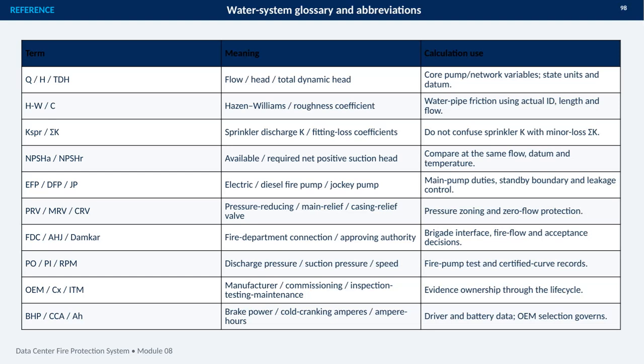This reference slide brings together the abbreviations used throughout the water system and fire pump calculations. The first group covers the core hydraulic variables. Q is flow, H is head, and TDH is total dynamic head. When using Hazen-Williams, remember that the roughness coefficient, pipe length, actual inside diameter, and flow all affect friction loss. A key distinction is between sprinkler K, which describes sprinkler discharge, and the fitting loss coefficients, shown as sigma K. They are not interchangeable. NPSH available and required must also be compared at the same flow, datum, and temperature.